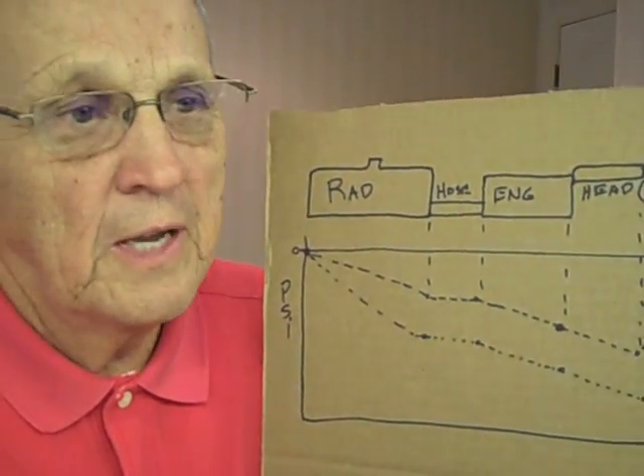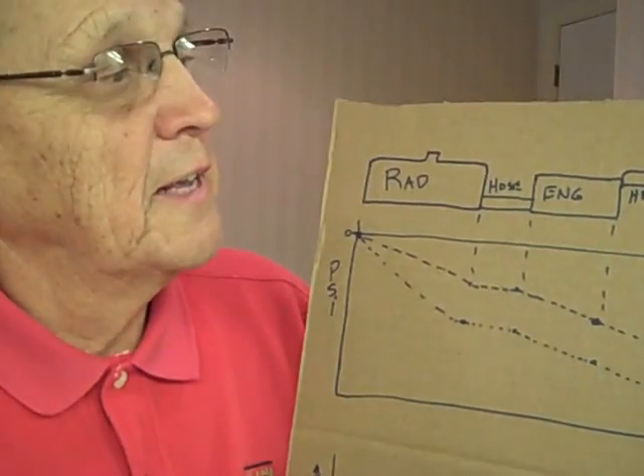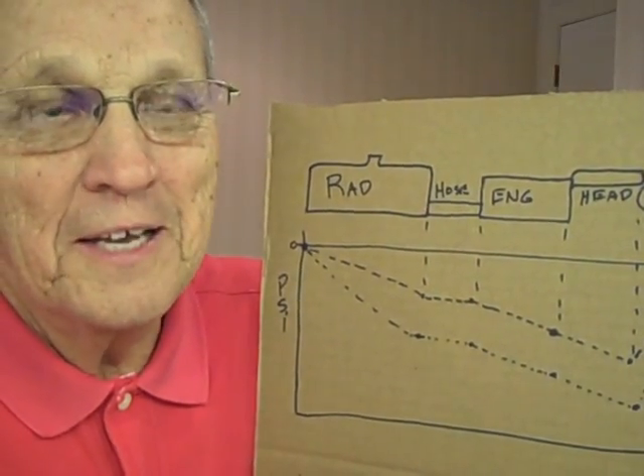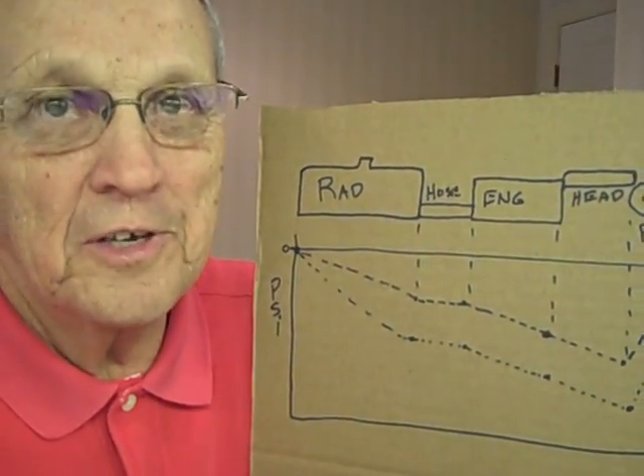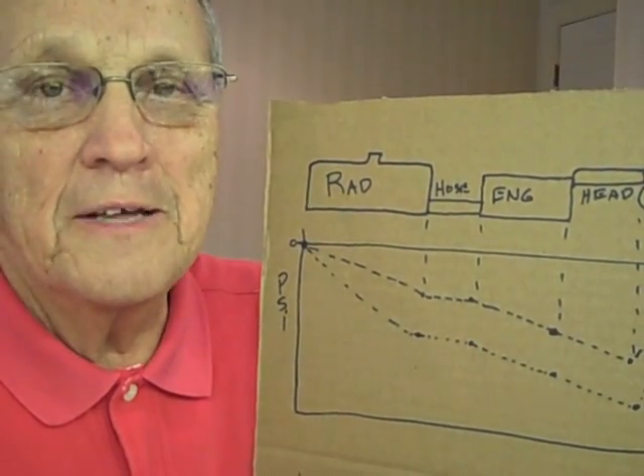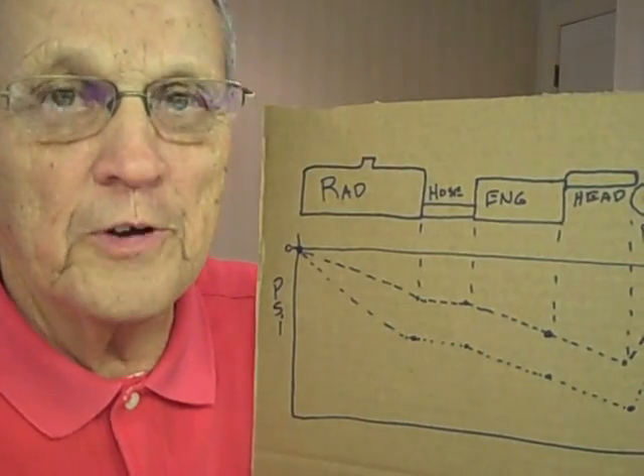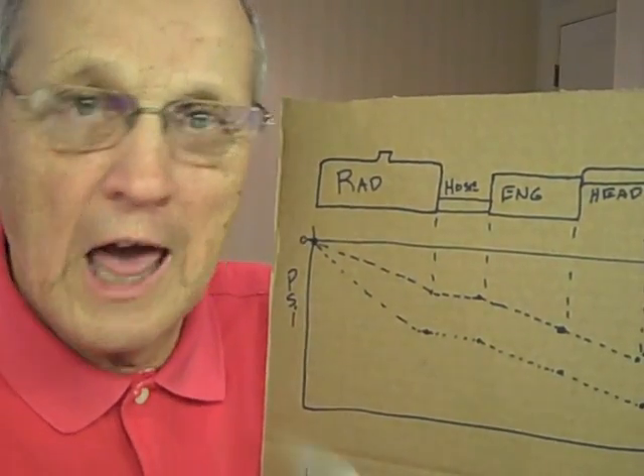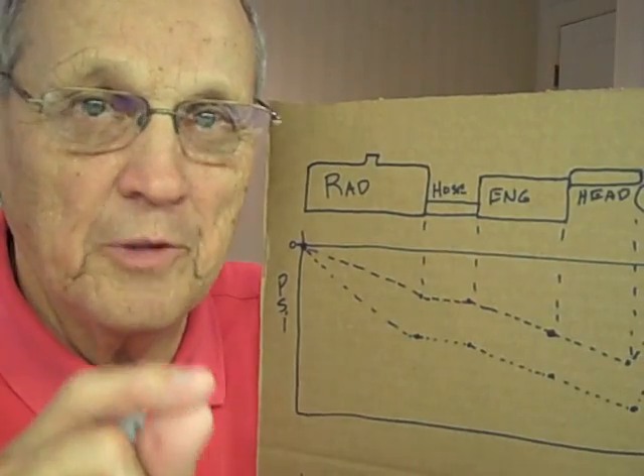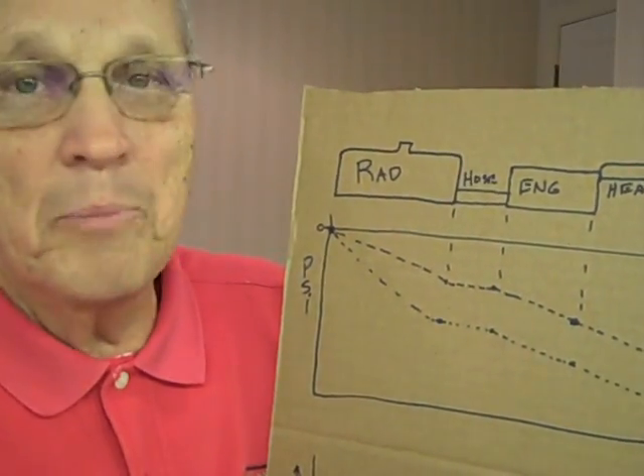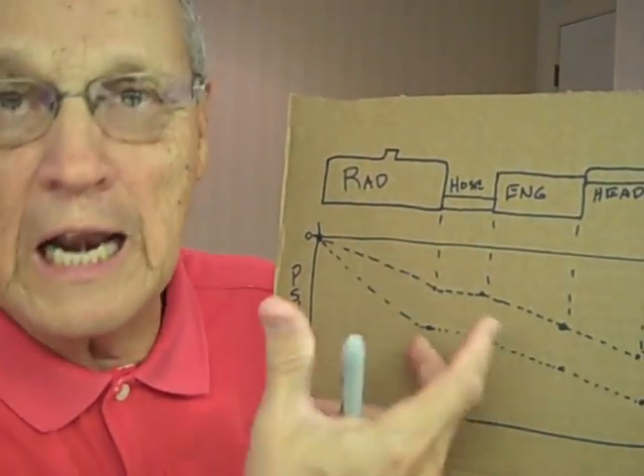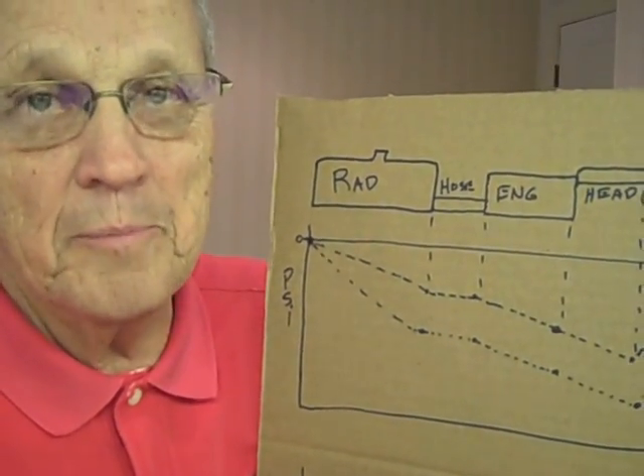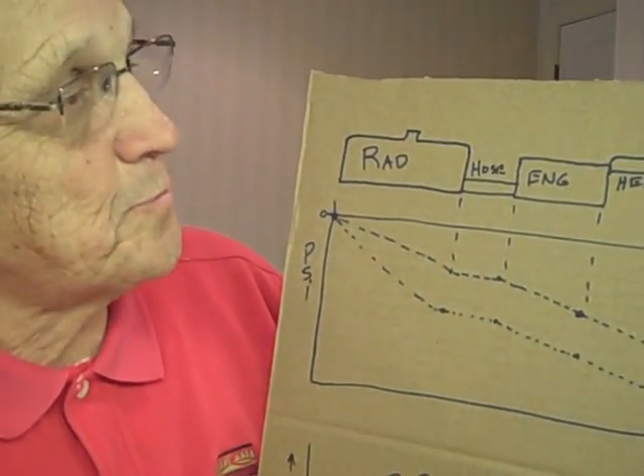While we're on this subject, I mentioned turbulence. There's another old saying you hear people say that water flows so fast through that radiator it doesn't pick up any heat. That's not true. Physics will tell you that the higher the turbulence of a heat transfer device, the better the heat transfer. It's more efficient the faster you can run that water through there. The more heat it's going to pick up. You're flowing so much more water through there, you're removing a lot more heat. So you can't run water through a radiator so fast it doesn't pick it up. Believe me, it will pick it up and you want to run high turbulence.